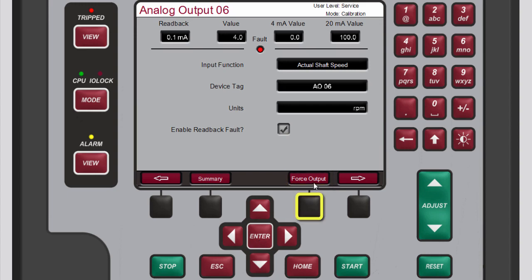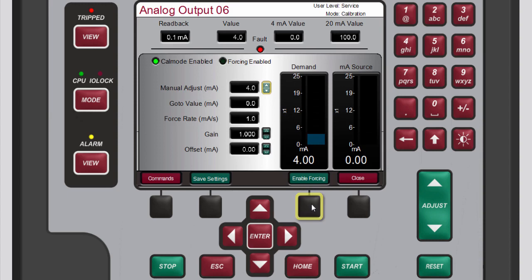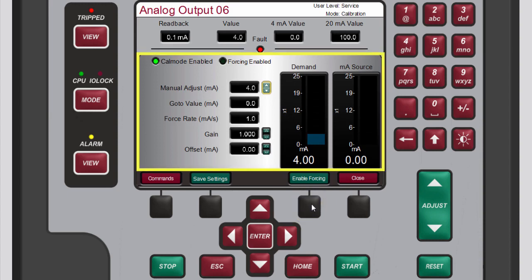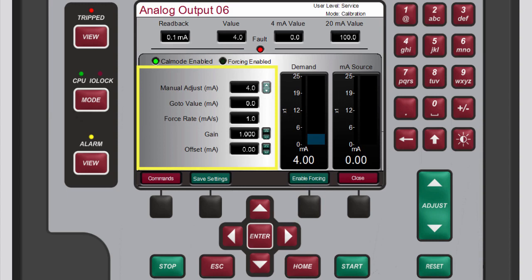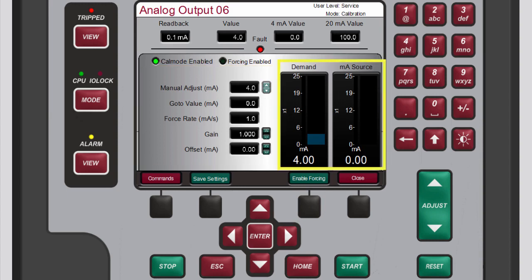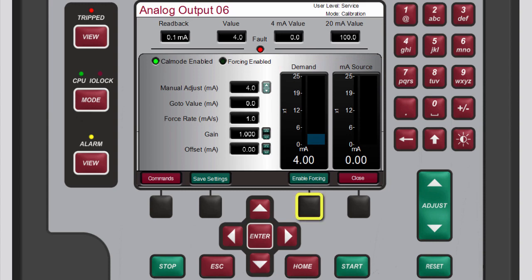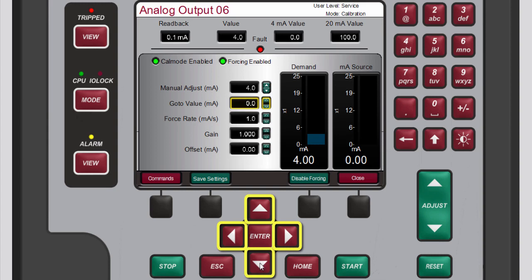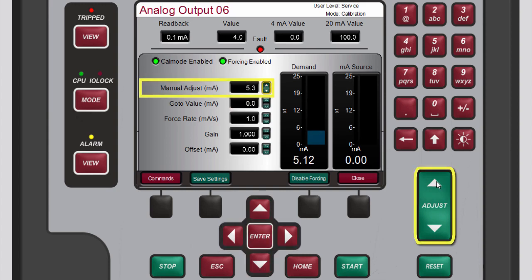Press the black function key below force output. A pop-up window opens showing values corresponding to the output forcing, as well as two visual gauges for the demand and milliamp source value. To enable forcing, press the black function key below enable forcing. You can now adjust the demand value of the channel. Use the navigation cross keys to highlight the manual adjust box, then use the adjust keys to change the value of the demand manually. The demand gauge should reflect the changes you make.